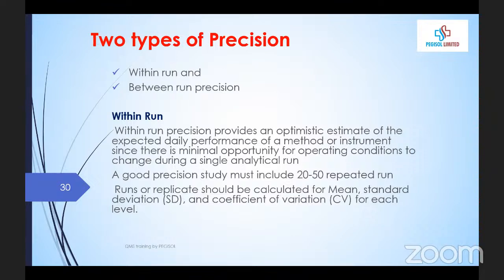Now, a good precision study must include a minimum of 20 to 50 repeatable runs. So you cannot do a precision study of 10 or 5. That's not precision. It has to be a minimum of 20. Why do we do 20? N has to be equal to or greater than 20 for statistical analysis to be valid. How many of you remember that? I remember a few weeks ago I was trying to teach this somewhere. I was drawing a bell shape. How many of you remember statistics, the bell shape, the distribution curve? So those are practical explanations of the things that you are learning, what we are doing now.